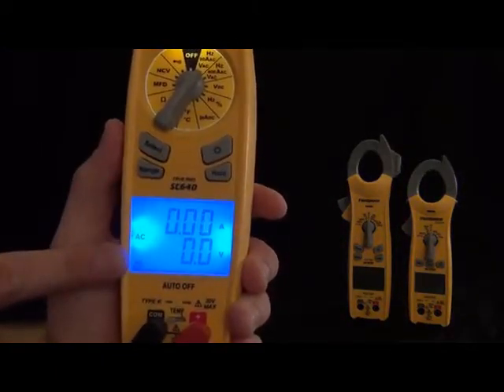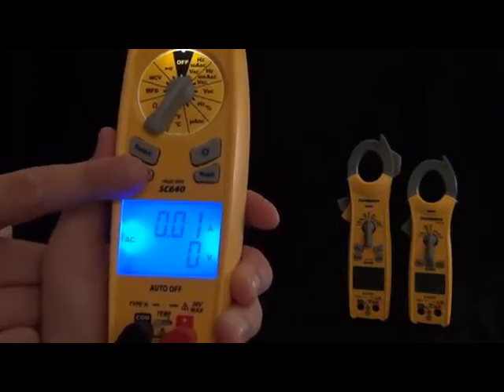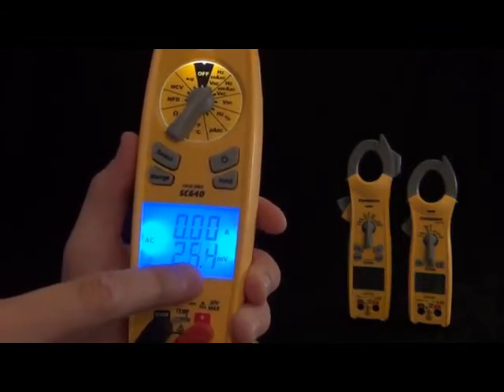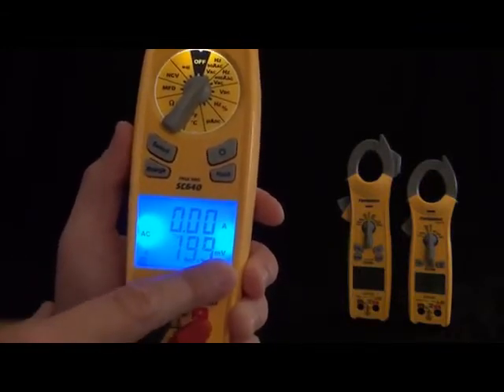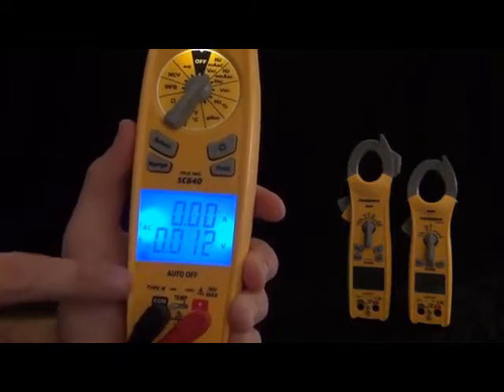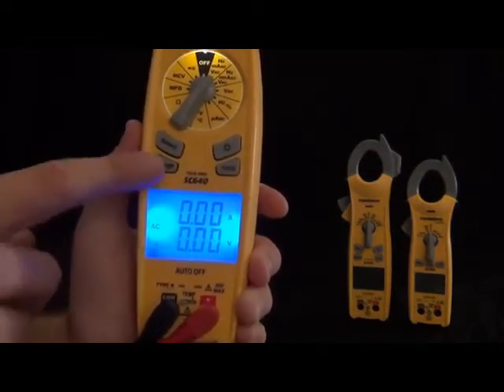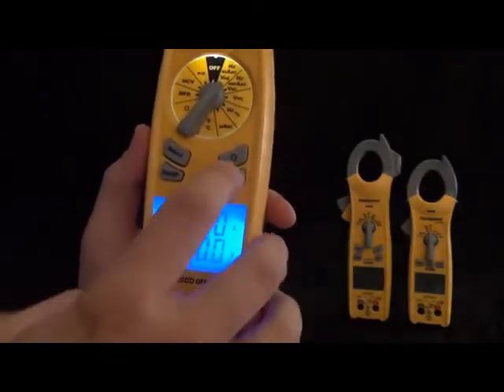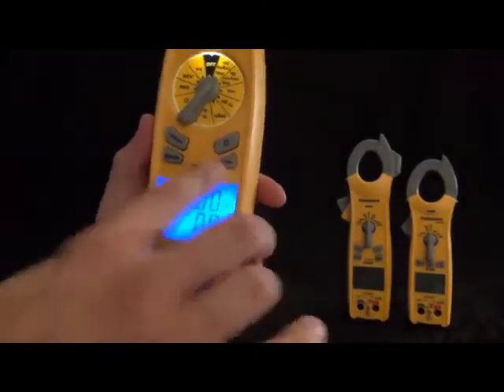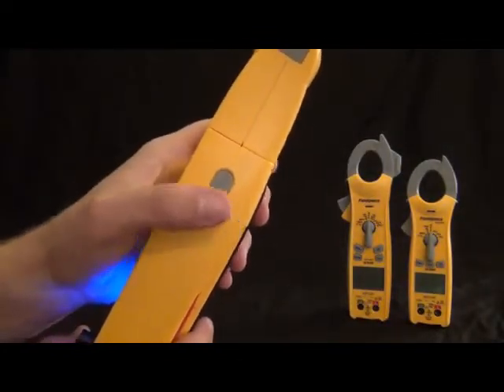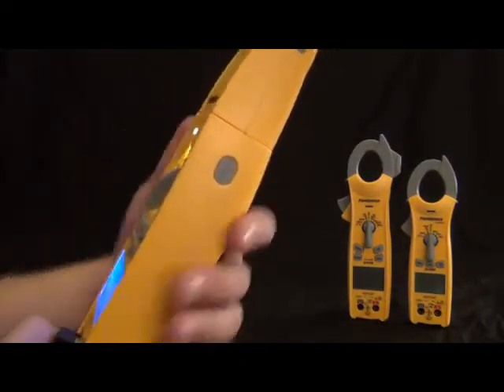Then we have the hold feature, so you can hold it, unhold it, and on the side, we have inrush current. So this puts it into inrush mode. When you're in the amps, the hertz and the amps, either one of these ranges, you can put it into inrush mode. What this is for is when you're doing compressor start-ups, you can see exactly how many amps it took to get that compressor going, or any motor for that matter.